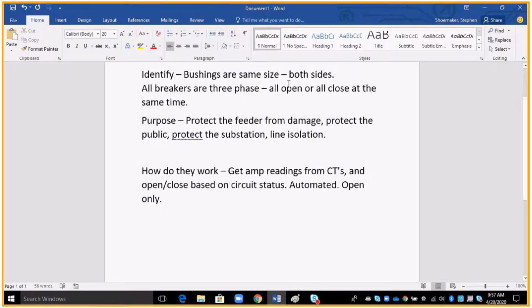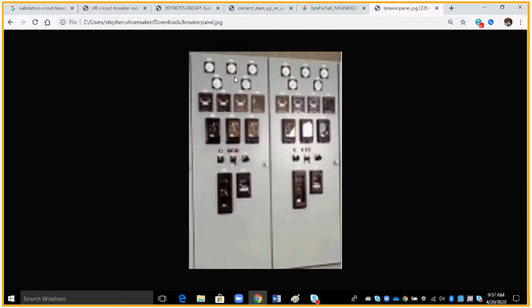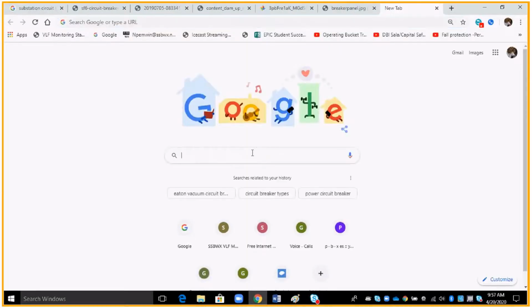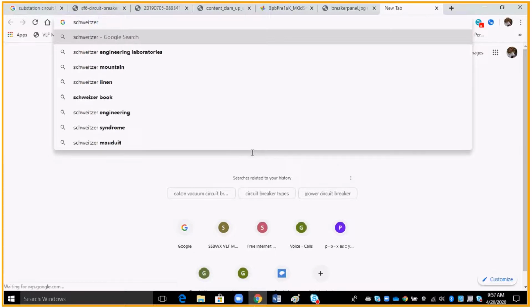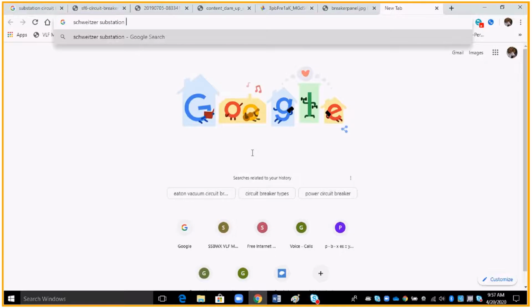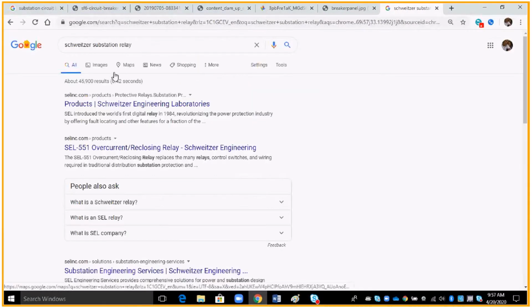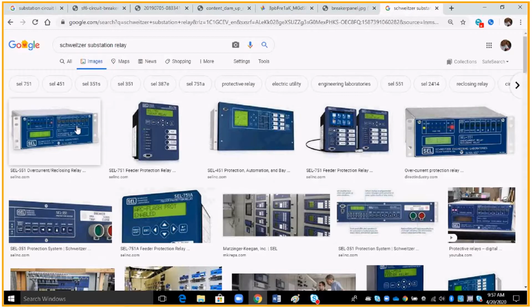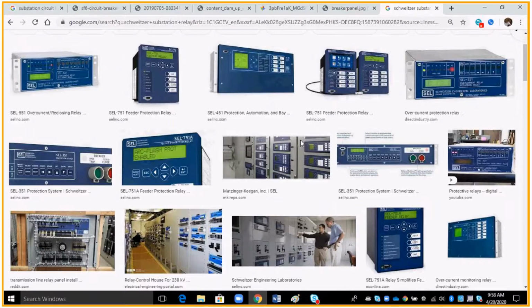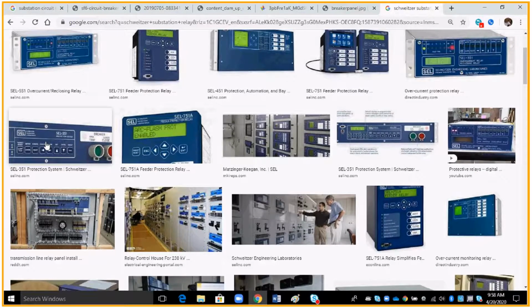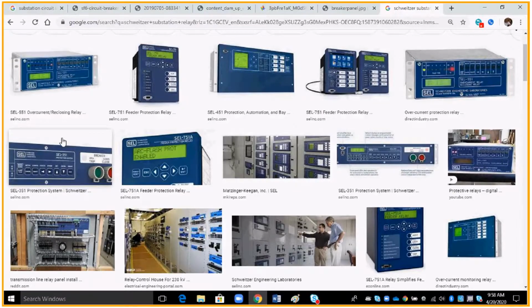So let's go to the breaker relay panel. You're going to see in this panel, this looks like a lot of stuff that's going on here. Firstly, there are two types. There's electromechanical, what you're looking at right here, and digital. Let me bring one up. You see there's a multiple variety. You've got a distribution reclosing relay, a feeder protection relay, just multiple types. What you're seeing right here, and I'll show you the ones that are most prevalent out there in the world, are these types for distribution. If you're going into transmission, we'll talk about the difference between the two in just a moment.